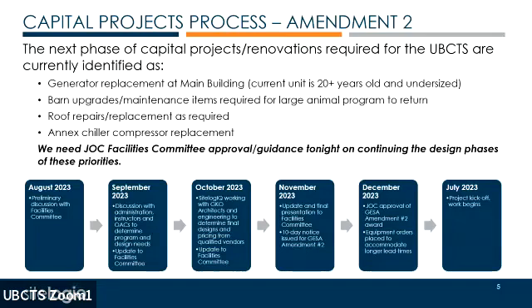That generator there, you said that's 175 to 185 kW. So if you're going to increase that, you also have to increase the pipe going in, the transfer switch, the wire size, the breakers, all of that. And a lot of that is aging already, getting into a non-compliant standard.